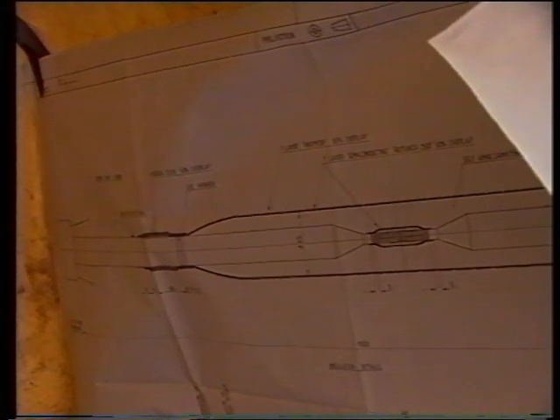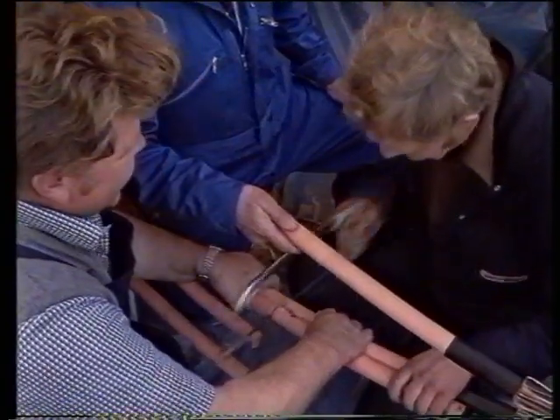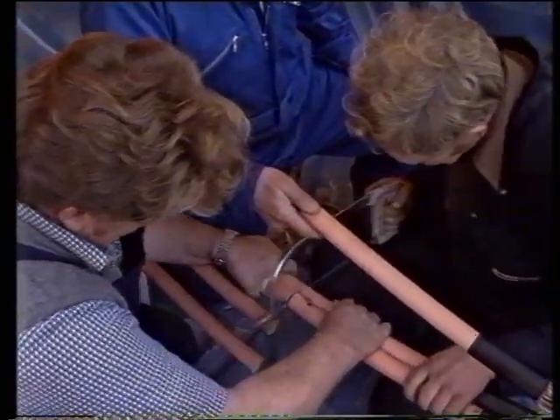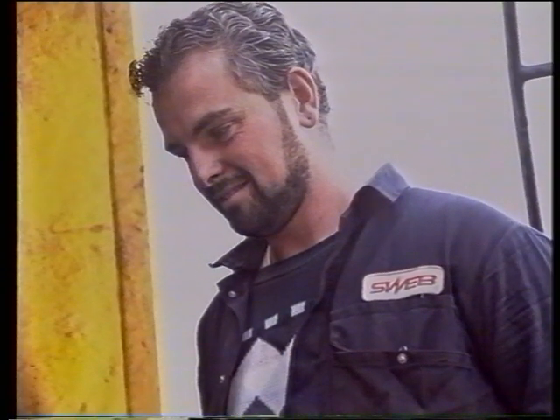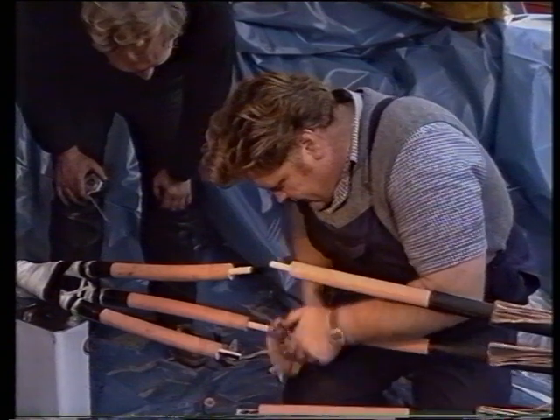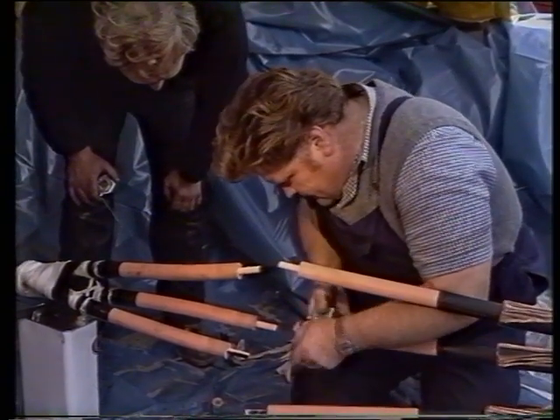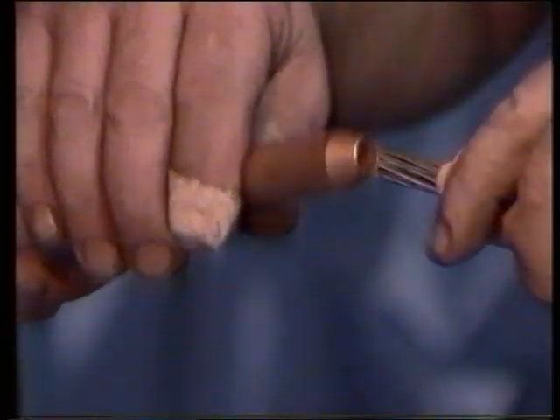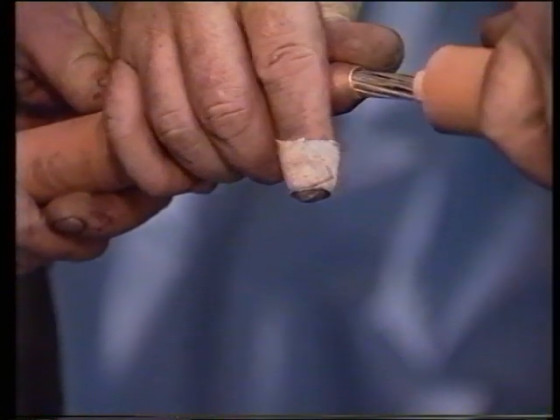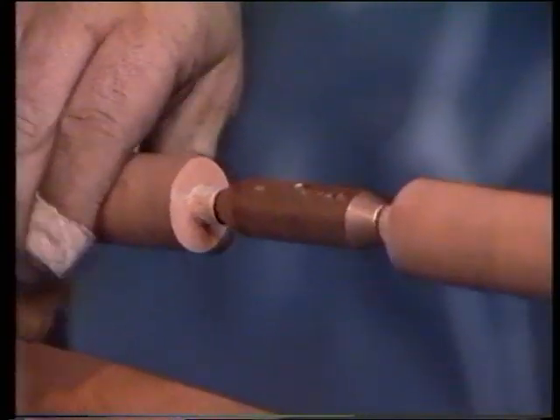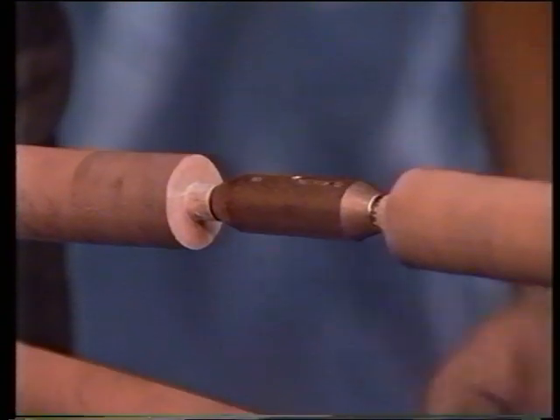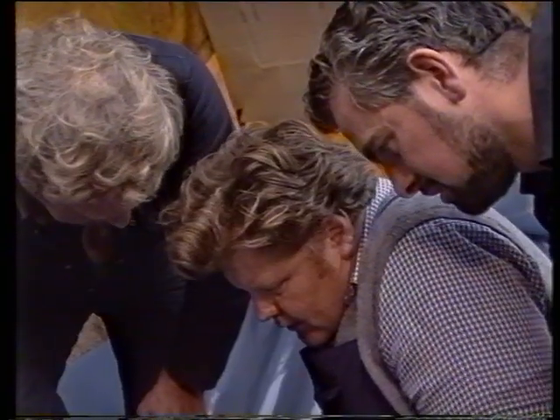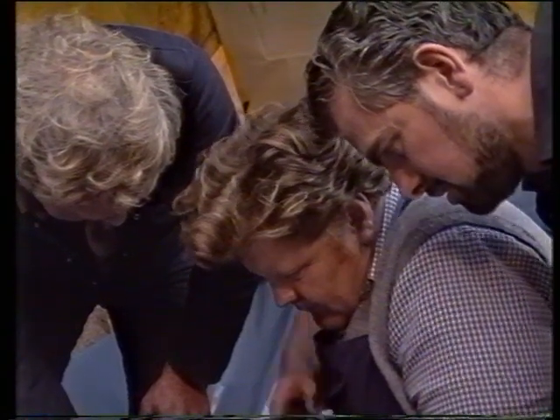A final check on the drawing, and the all-important cut through the cables is made. If this is wrong, there's no going back. But it's a perfect cut, and on they go to remove the insulation on both sets of cables to expose the copper cores themselves. The actual joint is made by a ferrule attached to both cores. To ensure a sound electrical connection, it's crimped down firmly and the joint packed with solder.